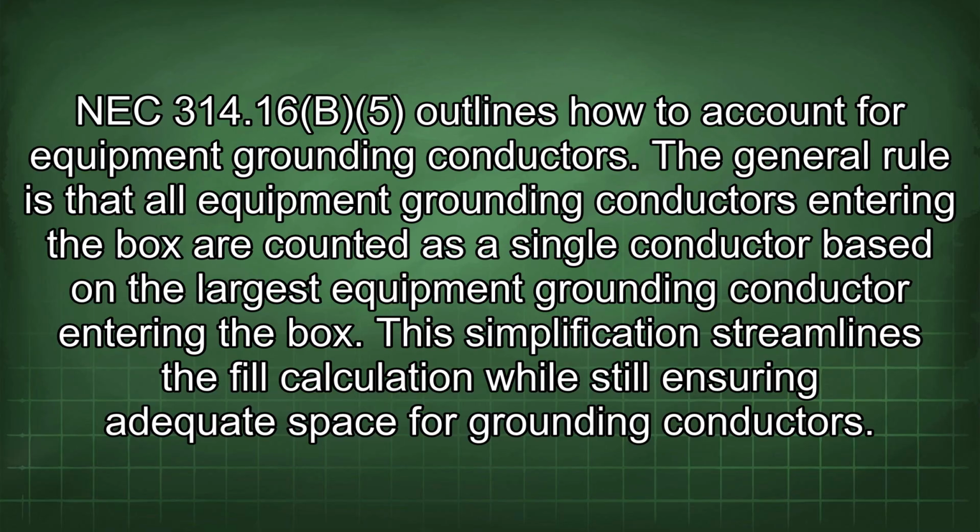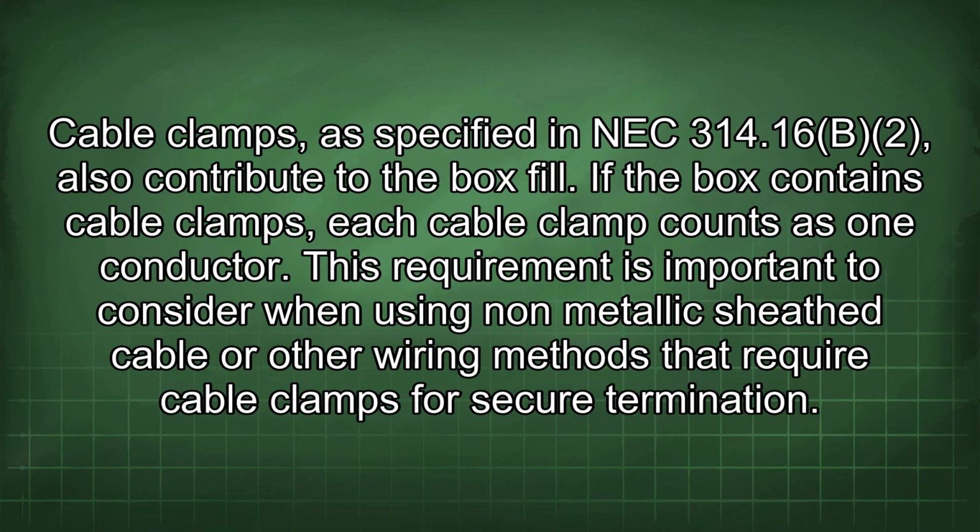This simplification streamlines the fill calculation while still ensuring adequate space for grounding conductors. Cable clamps, as specified in NEC 314.16(B)(2), also contribute to the box fill. If the box contains cable clamps, each cable clamp counts as one conductor.